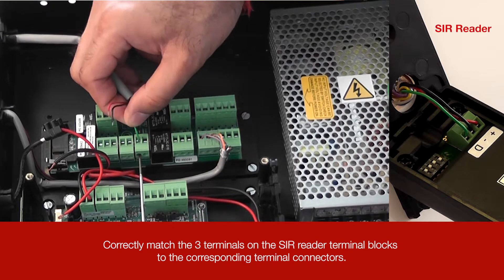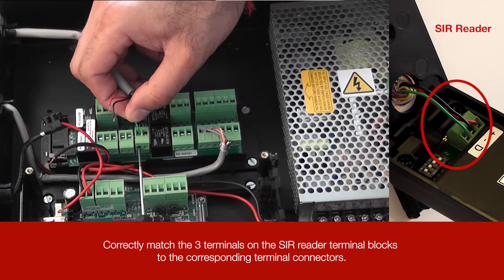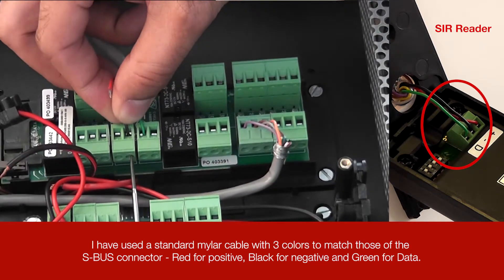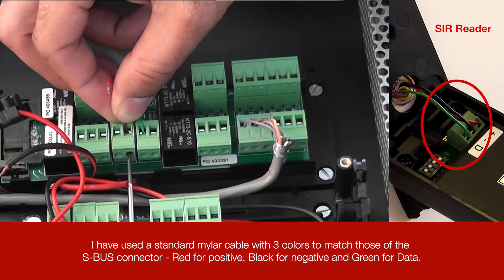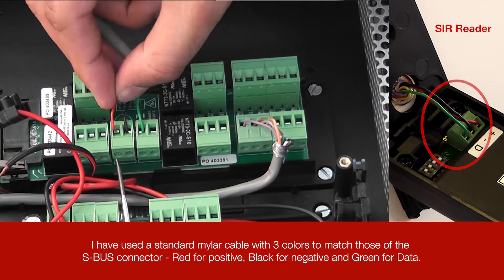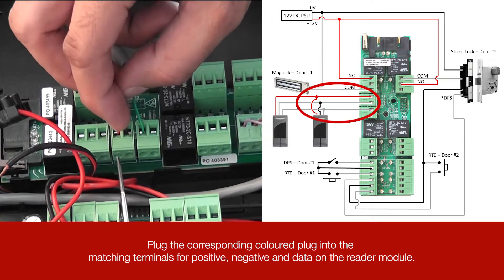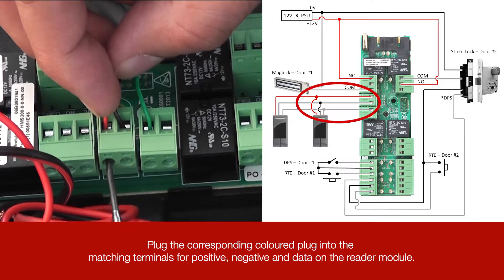Correctly match the three terminals on the SIR reader terminal blocks to the corresponding terminal connectors. I have used a standard mylar cable with three colors to match those of the SBUS connector: red for positive, black for negative, and green for data. Plug the corresponding colored plug into the matching terminals for positive, negative, and data on the reader module.